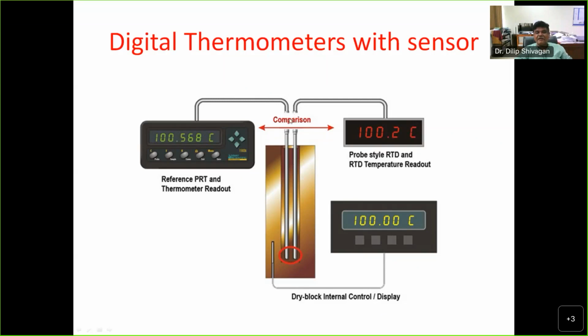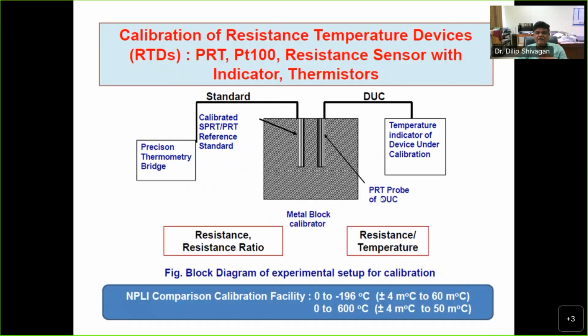Okay, then you take the temperature measured by the reference as the reference, and whatever deviation you observe on the DUC is then absolutely corrected. So this needs to be very, very highly stable. So if you want to have 0.1 degree Celsius calibration, definitely you need to have 0.03 as bath stability and uniformity. So that requirement is very, very stringent, and with that you can definitely get millikelvin uncertainties for fixed point calibration; for comparison calibration you can go for 4 mK to 60 mK. So depending on the range, we can certify it with very, very high levels.